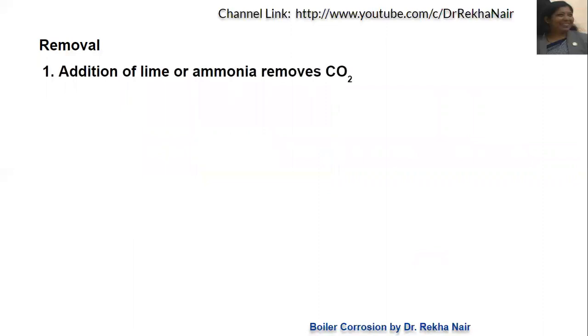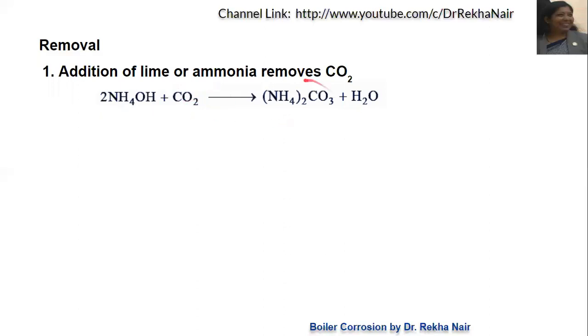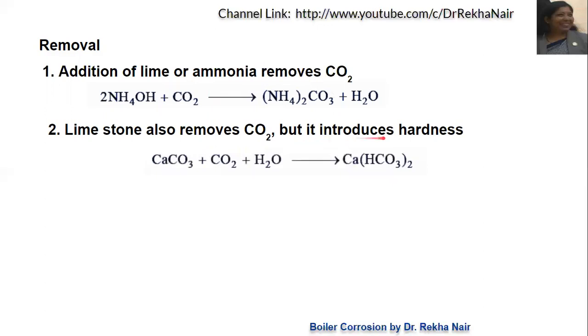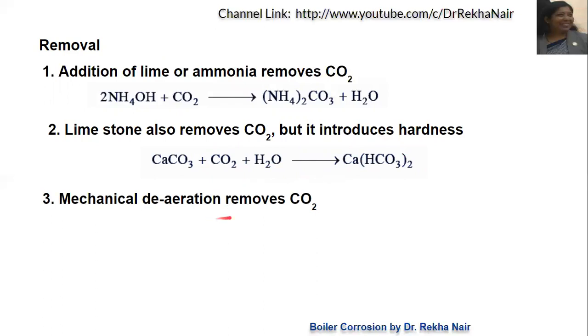For the removal of carbon dioxide, we can add lime or ammonia, because ammonia reacts with carbon dioxide to form ammonium carbonate, consuming the carbon dioxide. Limestone also removes carbon dioxide by reacting with it to form calcium bicarbonate, but because it introduces hardness into the water, we generally do not prefer that method. Mechanical de-aeration and preheating, as explained in the case of oxygen, can also be used to remove carbon dioxide. So both mechanical de-aeration and preheating can be applied for removal of both oxygen and carbon dioxide.